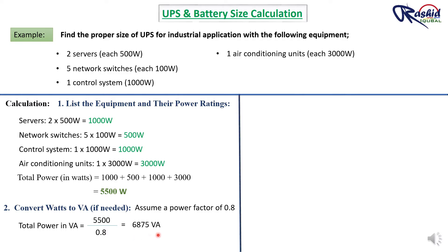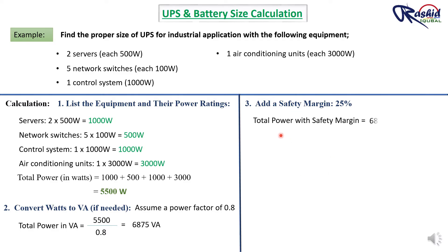Now we need to add a safety margin — typically 25% or 30%; here I use 25%. Total power with safety margin equals 6875 multiplied by 1.25, which gives us 8593 VA.